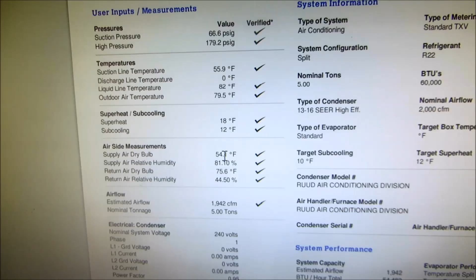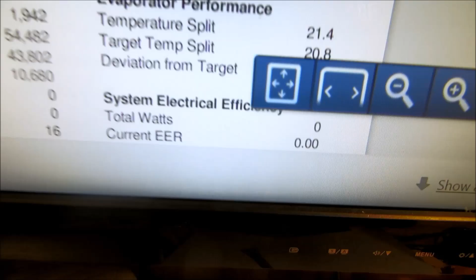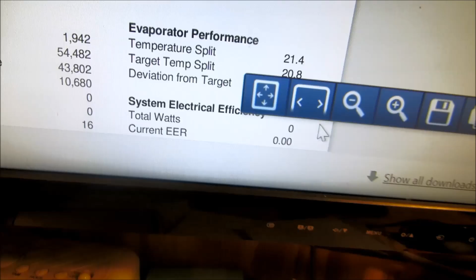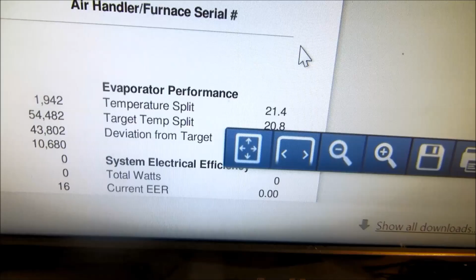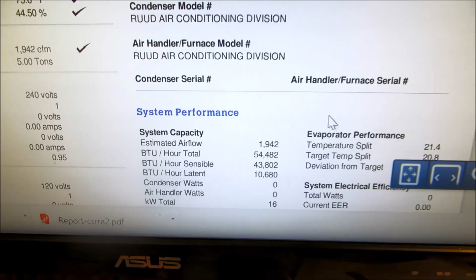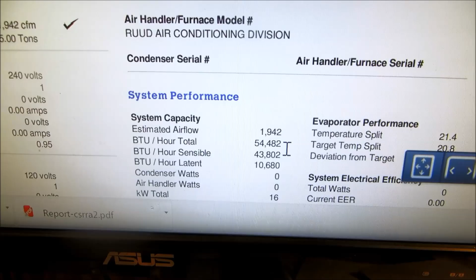Supply air dry bulb, temperature split over here. My target was 20 and my temperature split was 21.4. Don't forget now, I got no supply or return plenum on that, well not really a lot, so estimated airflow I'm just below 2,000, which is good.